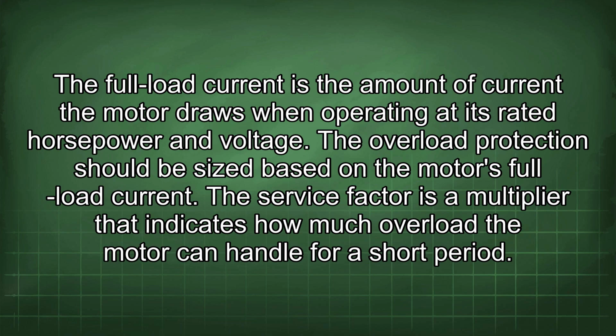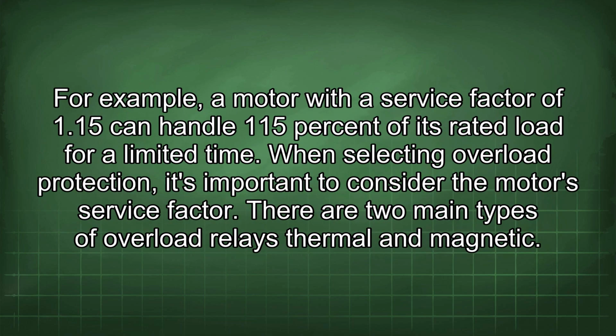The service factor is a multiplier that indicates how much overload the motor can handle for a short period. For example, a motor with a service factor of 1.15 can handle 115% of its rated load for a limited time. When selecting overload protection, it's important to consider the motor service factor. There are two main types of overload relays: thermal and magnetic.